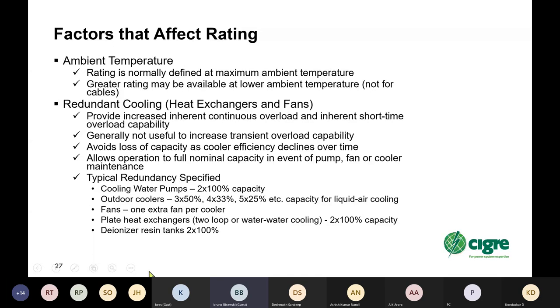So typical redundancy that might be specified in the cooling system: cooling water pumps, 2x100% capacity; outdoor coolers, depending on the size of the device, you could have 2x100, 3x50, 4x33, 5x25, etc. capacity for liquid to air cooling. Fans, you might have one extra fan per cooler. Plate heat exchangers, 100% capacity. Deionizer resin tanks for the pure high purity water in the cooler electronics, 2x100%.